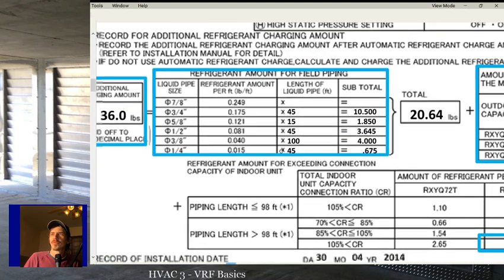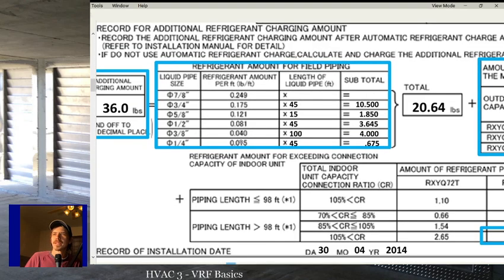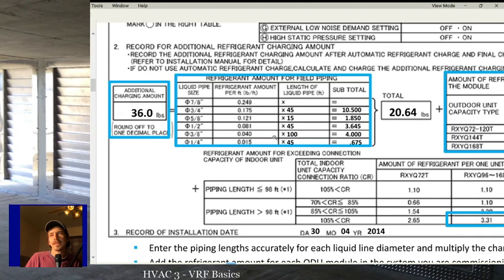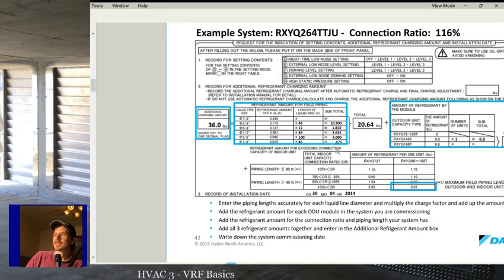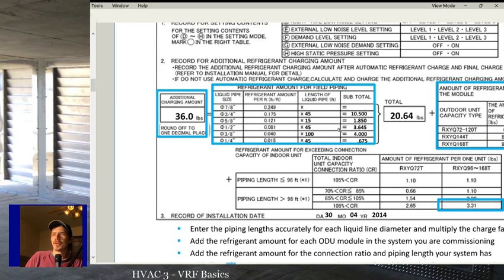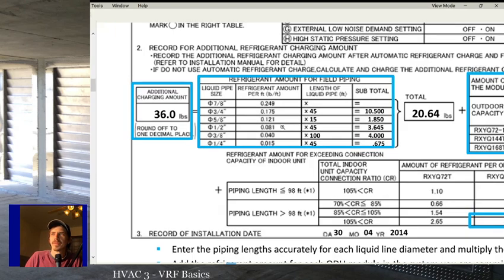Alright, here you go. Refrigerant amount for field piping, 3/8 line set, 0.04. Maybe it does change a little bit more than I thought. I swear 0.06 most manufacturers, or maybe they changed this, I don't know. Anyway, it's generally pretty close though, no matter what you're doing. Field piping for any liquid line, 0.01 ounces per foot for a 1/4 inch, 0.04 ounces per foot, or pounds per foot, sorry, maybe that's what it is, 0.6 ounces or 0.04 pounds, whatever it turns out to. But this is get you close, you know what I mean?